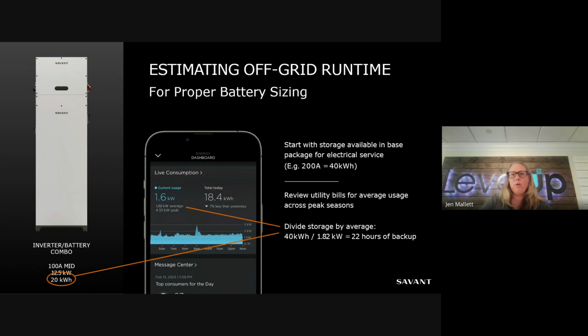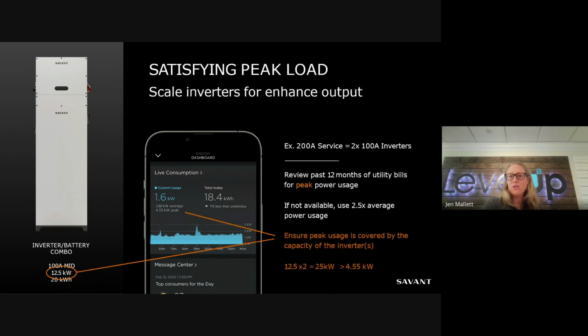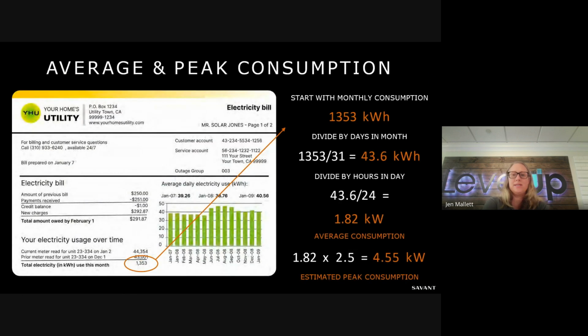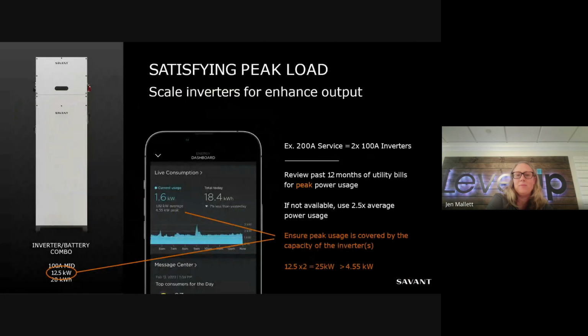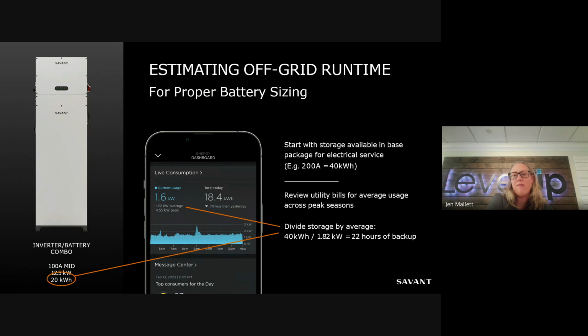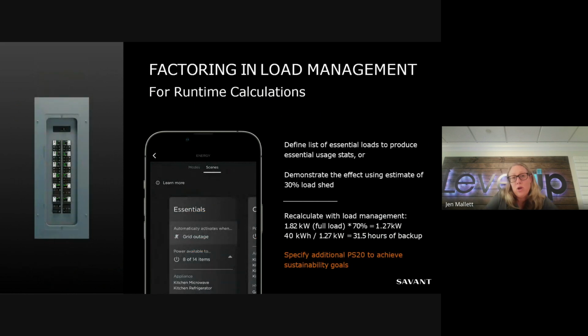But again, that 1.82, if I go back to this slide here, is the average consumption, not the peak consumption. So that's something to consider. But you generally will have about 22 hours of backup for this off-grid runtime. When we factor in load management and look at runtime calculations, what we're trying to understand from the client is, what are the things that are most important to them? Every individual or family lives in a house a little differently, right? So understanding what the essential loads are as part of the design consultation is really critical.